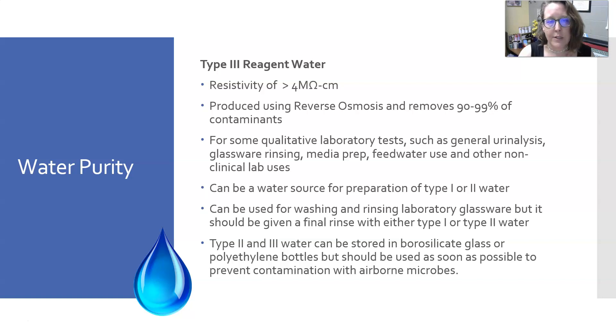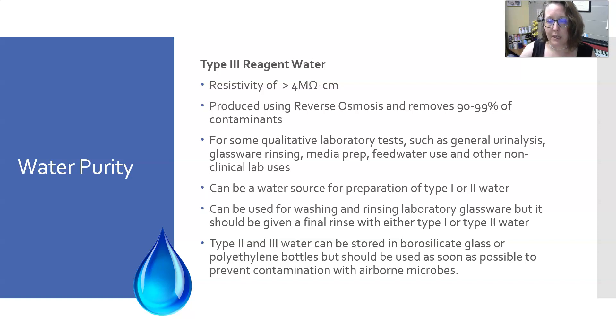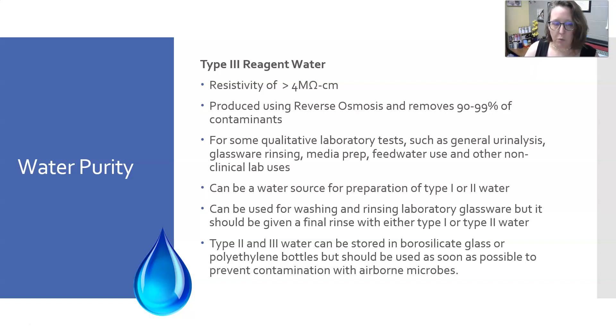Type 3 reagent water has a resistivity of greater than 4 mega-ohms per centimeter. It is produced using reverse osmosis, which removes 90% to 99% of contaminants. It is used for some qualitative lab tests such as general urinalysis, glassware rinsing, media prep, and feed water use — meaning it can serve as a water source for the preparation of Type 1 or Type 2 water. It can be used for washing and rinsing lab glassware, but should receive a final rinse with Type 1, Type 2, or clinical lab reagent water. Type 2 and Type 3 water can be stored in borosilicate glass or polyethylene bottles, but should be used as soon as possible to prevent contamination with airborne microbes.